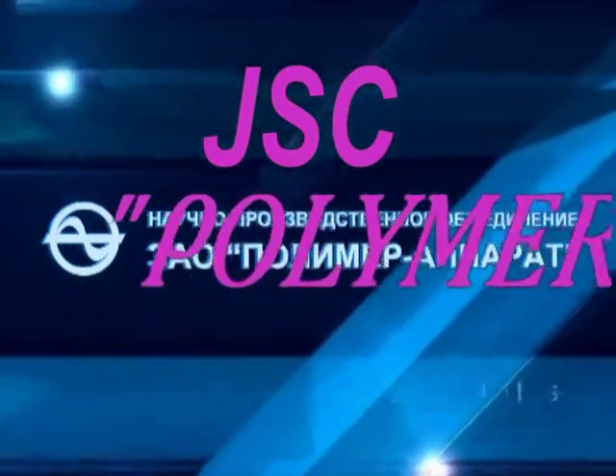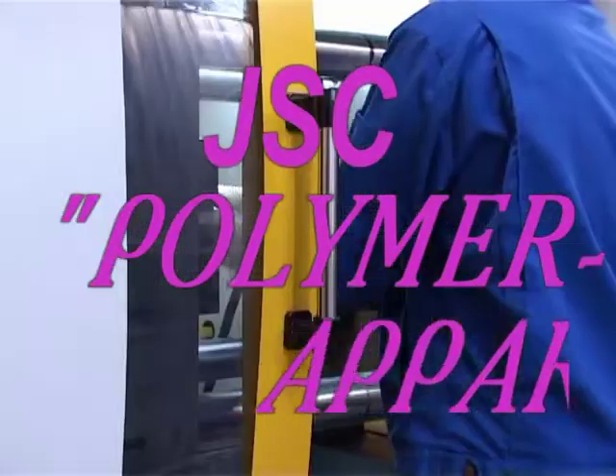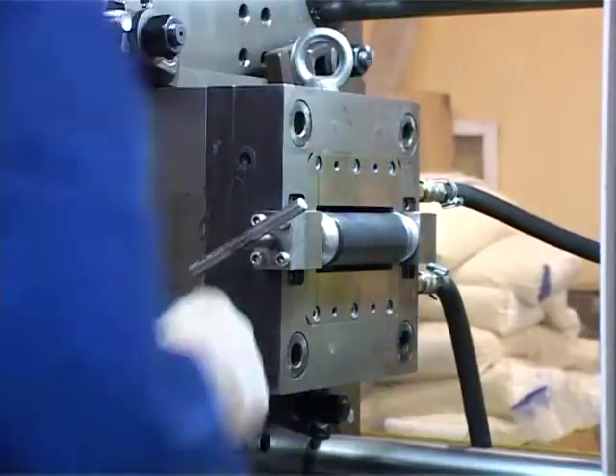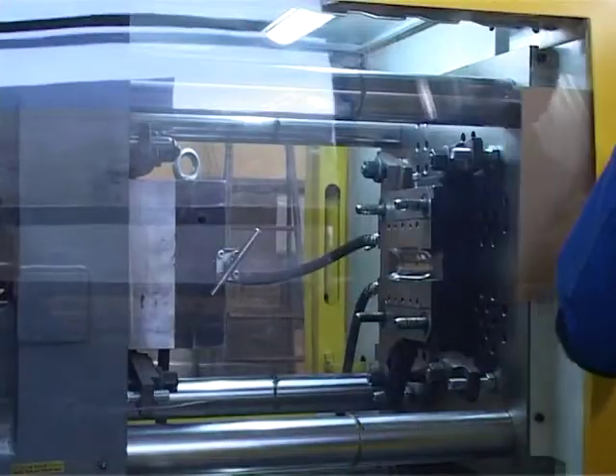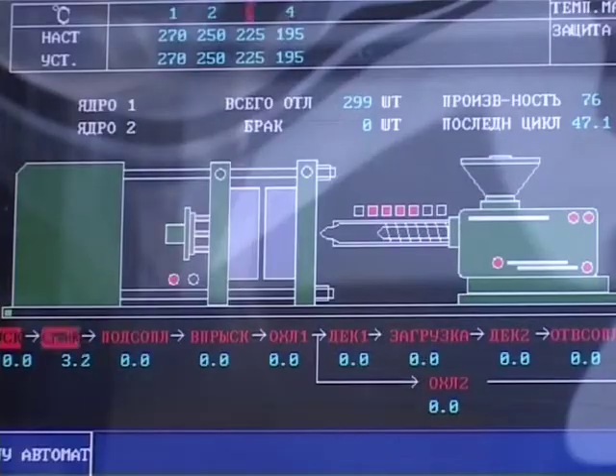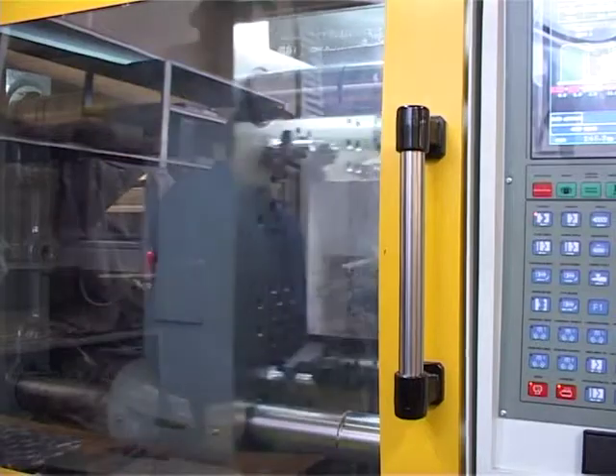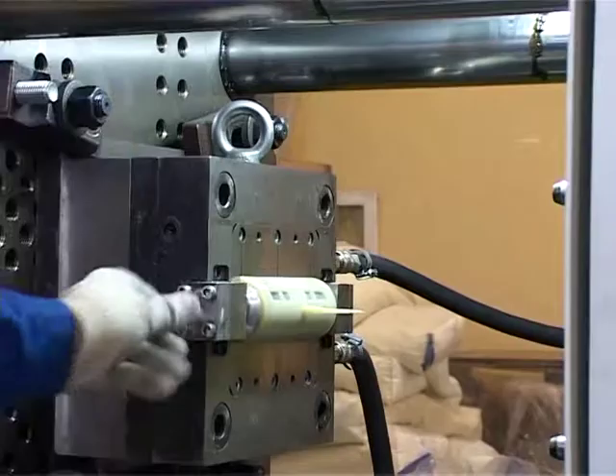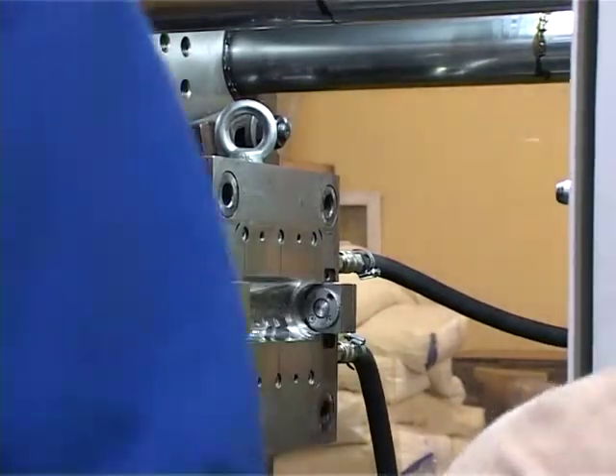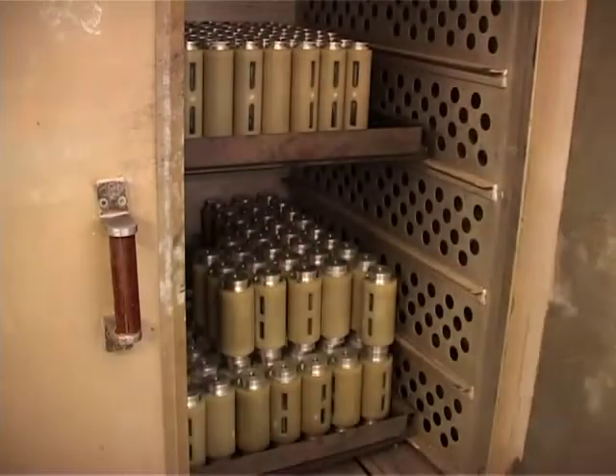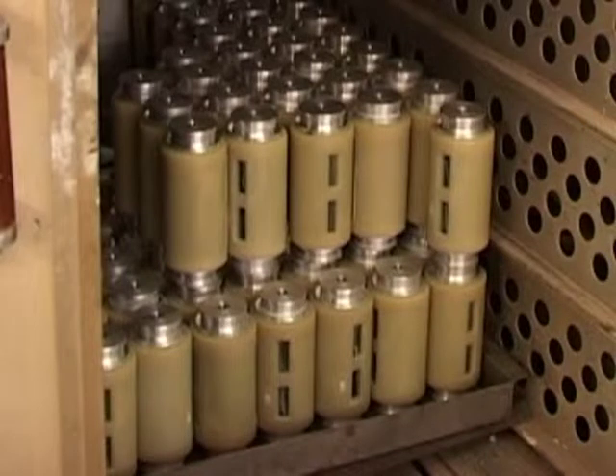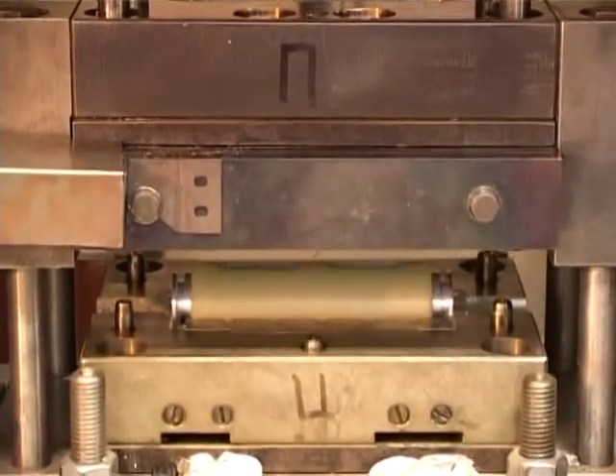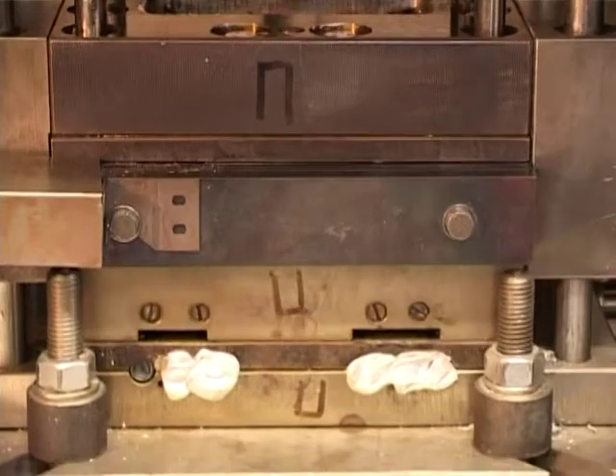Manufacturing of 6 to 10 kV surge arresters. Columns of varistors with aluminum flanges at the ends are placed in a thermoplastic automated machine and housed. Explosion safety valves are mounted along the housing of the future arrester. Workpieces are covered with adhesive composite and heated. Then the workpiece is coated with organic silicon rubber using the compression method.